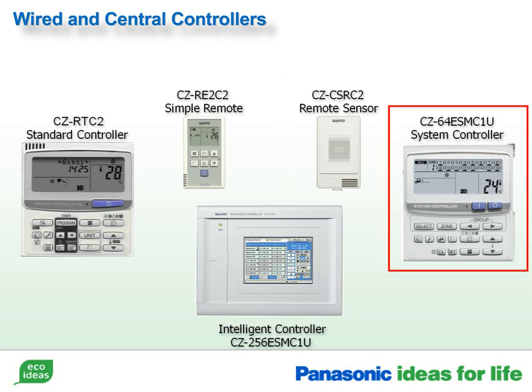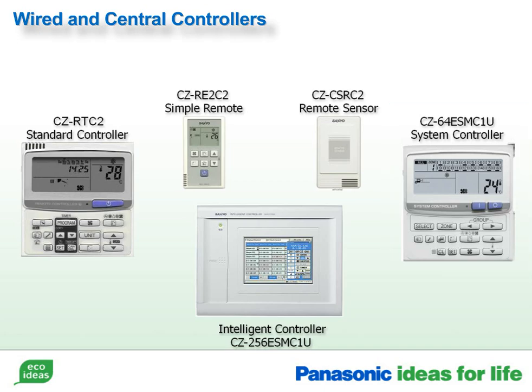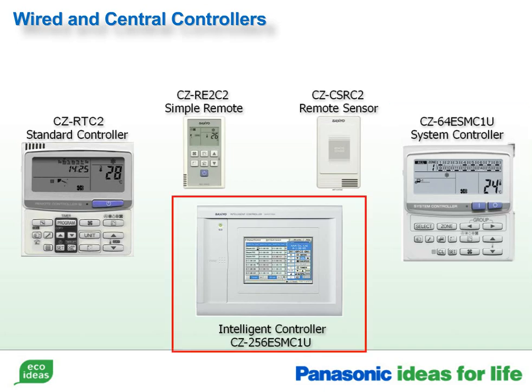The system controller is a central control device that can control up to 64 indoor units. It does not include timer functions, but it can be set to prohibit local controller functions. For example, it can prohibit a local controller from turning on or off, changing set point, or modes. The intelligent controller is a central control device which can control up to 128 indoor units. It has a touch screen and it is web-enabled. It can perform all of the functions allowed by the other controllers.